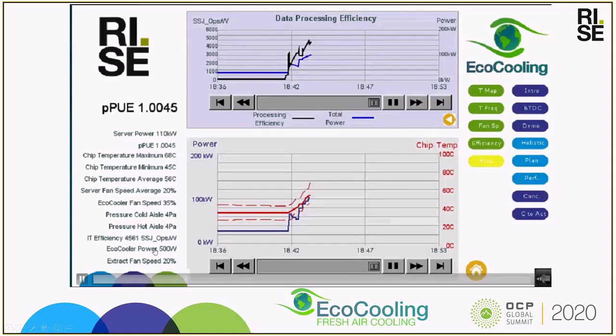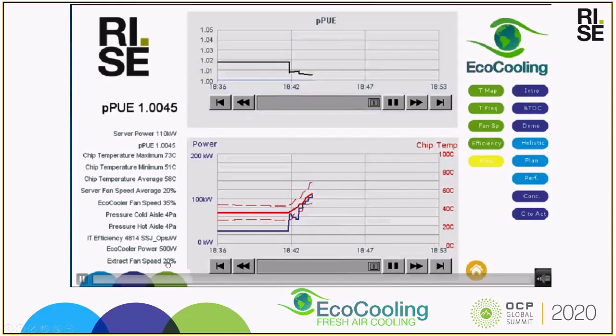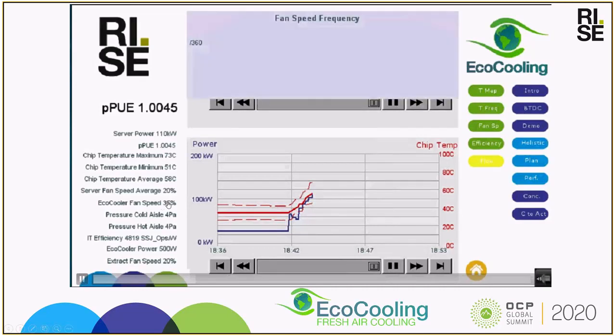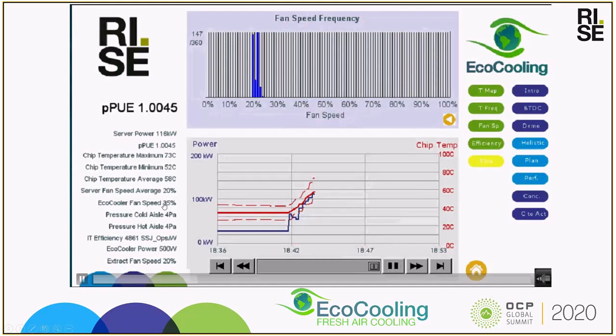The EcoCooling fans are using 500 watts at the moment, so we have two extract fans which are operating at 20% and two supply fans which are operating at 35%. The supply fans are operating at 35% based on the fact that the average server fan speed is at 20%.